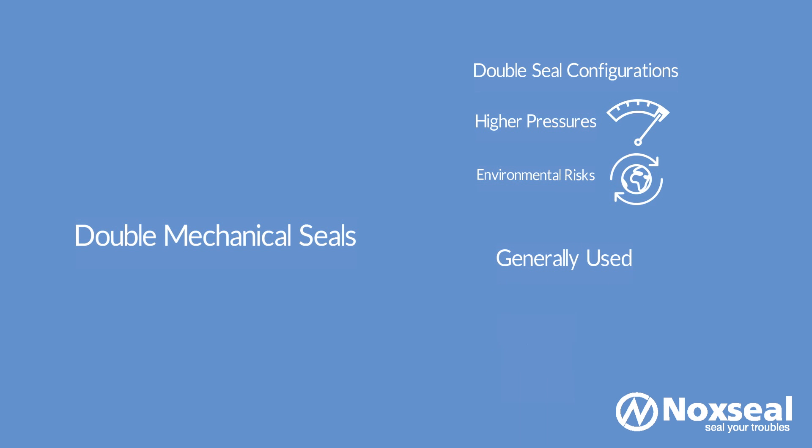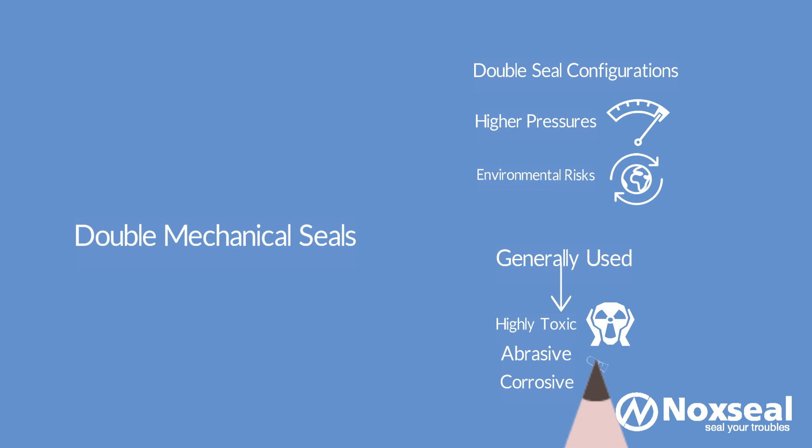Double Seals are generally used with unstable, highly toxic, abrasive, corrosive and viscous fluids. An advantage of a pressurized double seal is that it allows the use of a less exotic inboard seal material so they are less expensive to purchase and maintain.